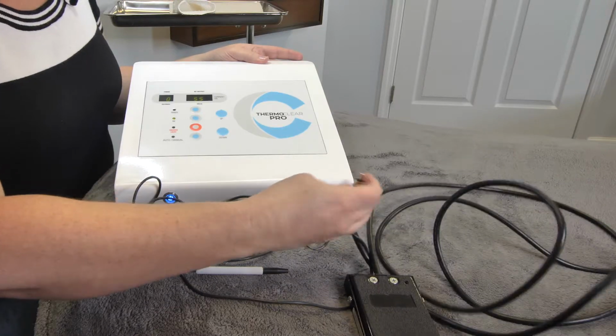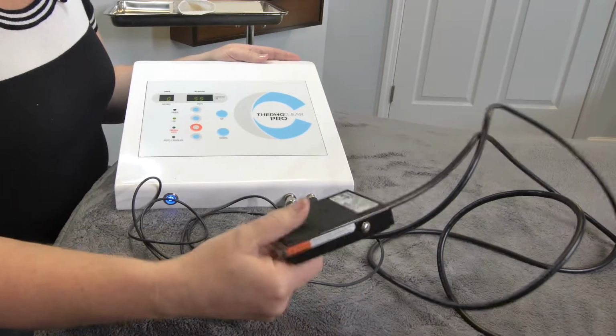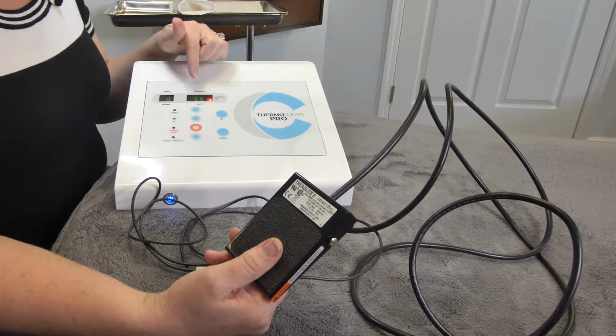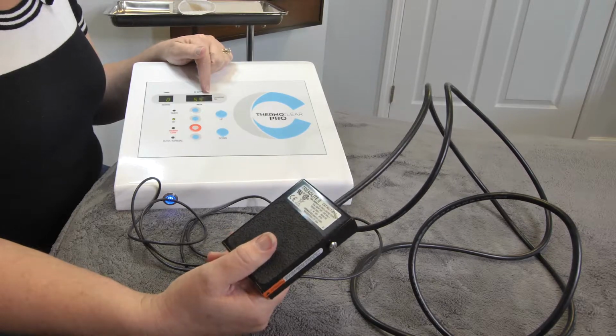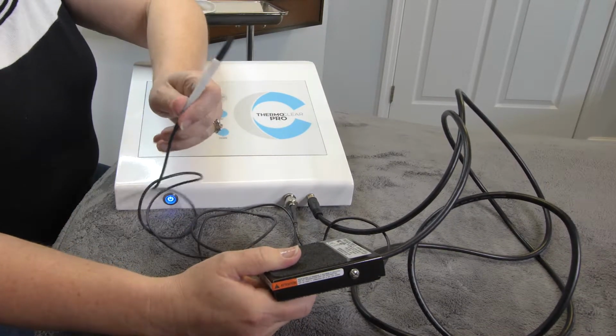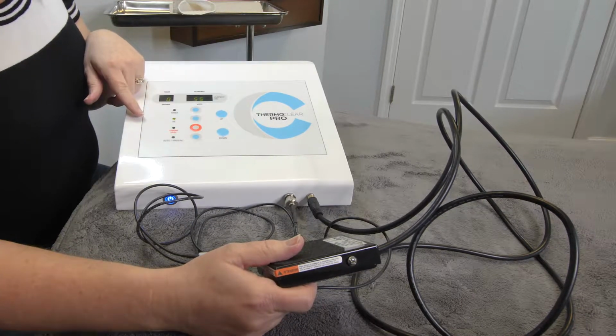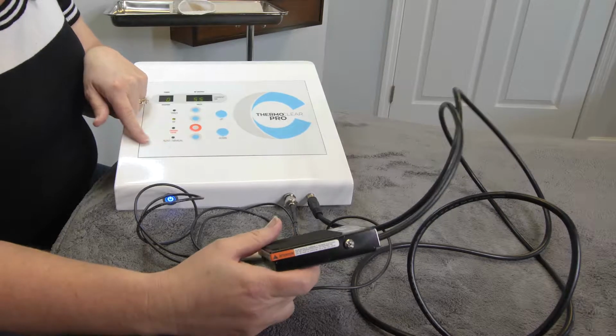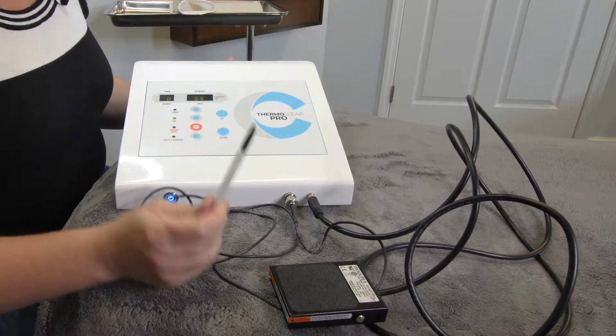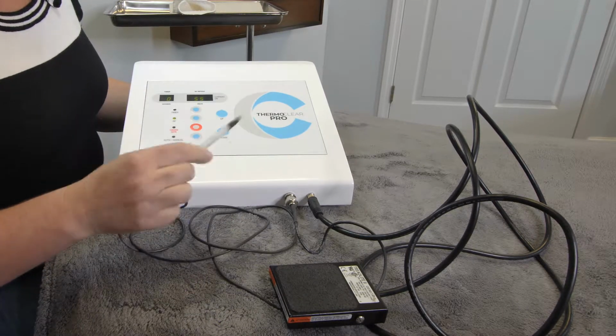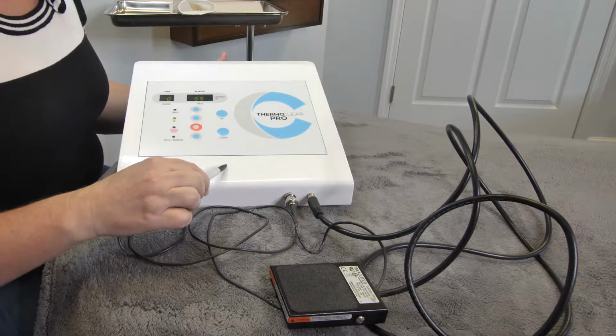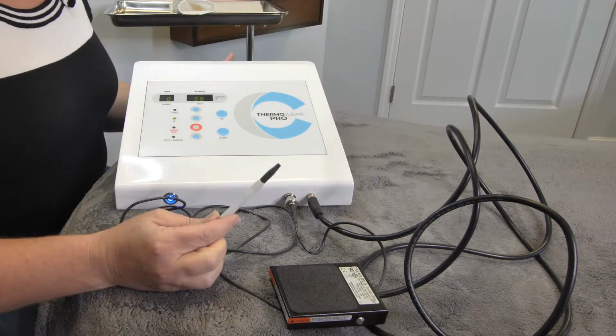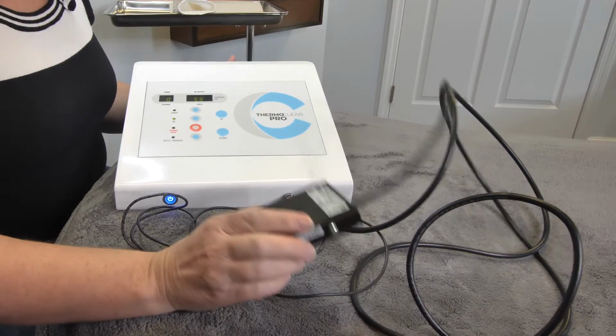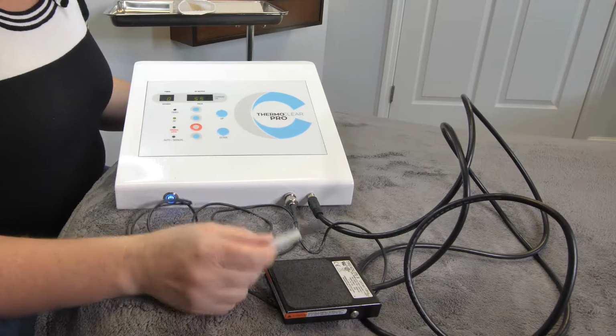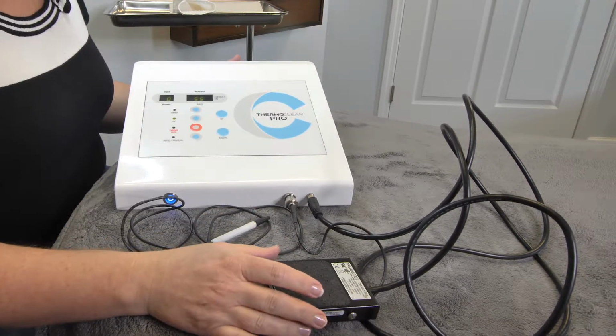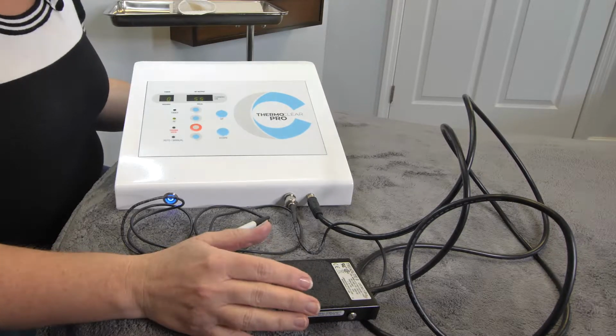This has a foot pedal, and you want to put this down on the floor somewhere that is close by so that you'll see when I turn it on, it indicates on here that the current is on, which means there's current flowing to this probe piece. The options for the foot pedal are auto and manual. Auto would mean that you are only conducting current when it picks up that you are touching something. I'm a manual kind of girl, so I like to only know that I'm getting current whenever I'm pressing the pedal. It's completely your preference, but it's designed to reduce fatigue on the user and just as a safety option.